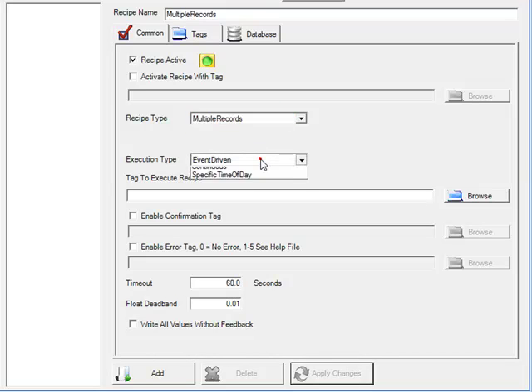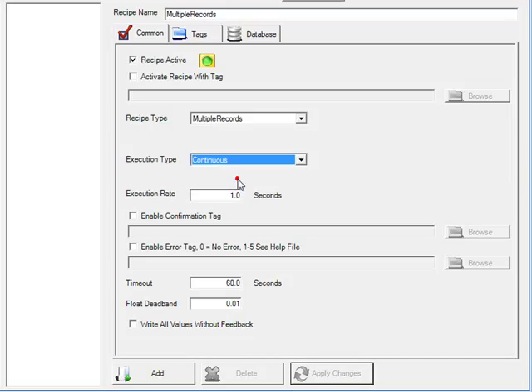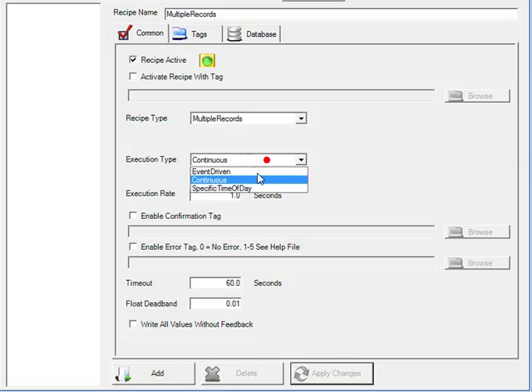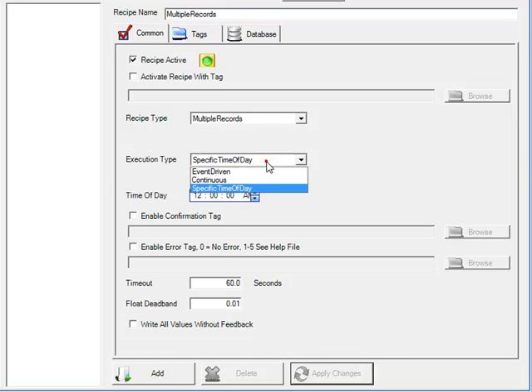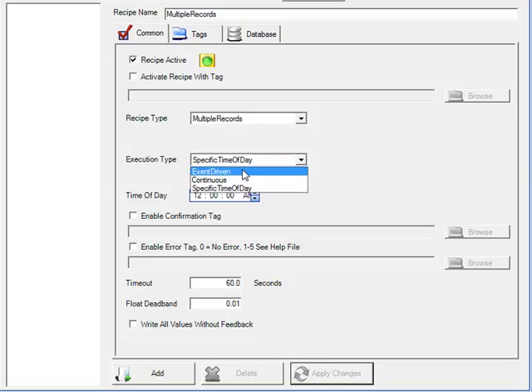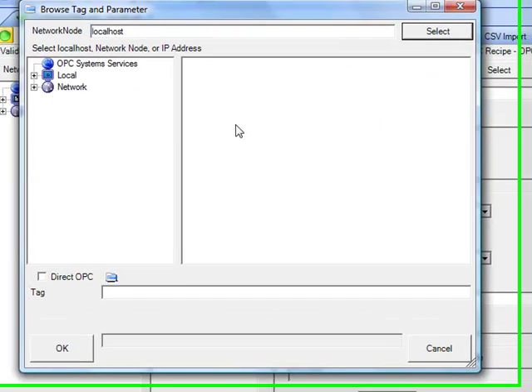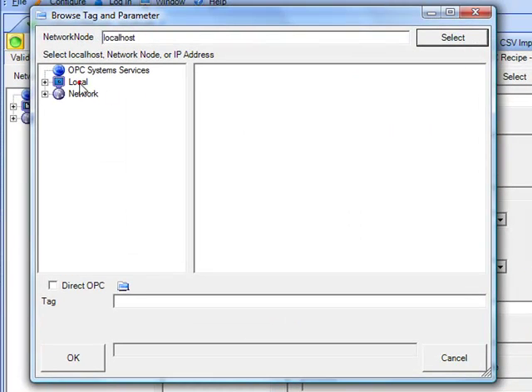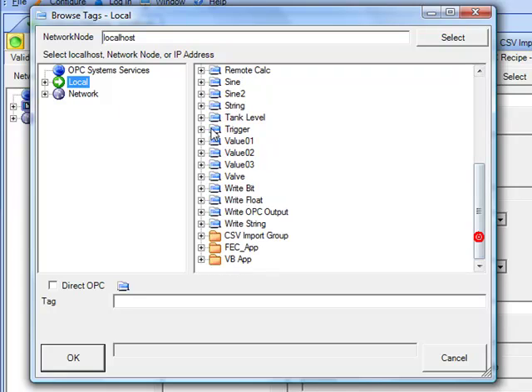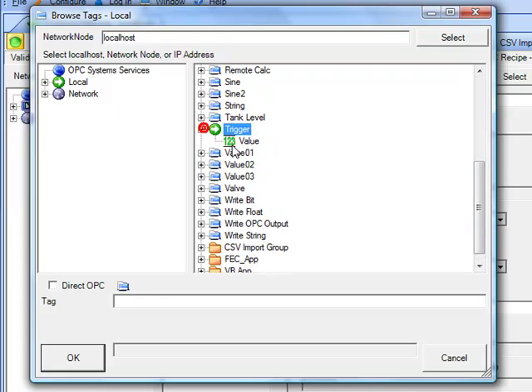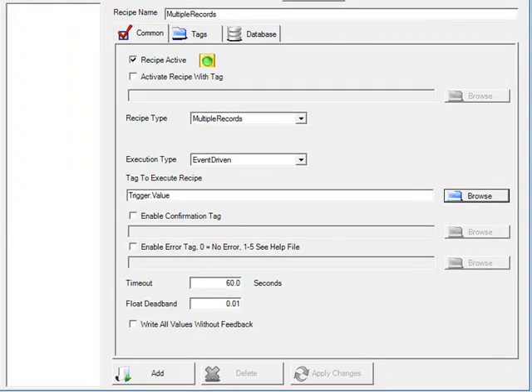Under the execution type, you can choose event-driven, continuous to execute at a specific interval, or specific time of day to execute at a particular time of the day to execute the recipe. We'll leave the default of event-driven. We can then browse for an opcsystems.net tag to trigger the recipe execution. We'll select the local service, and go down to the trigger tag and select Value parameter. When that value transitions from false to true, it will then execute this recipe.